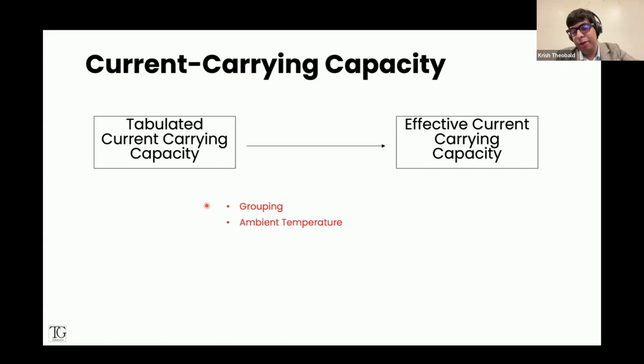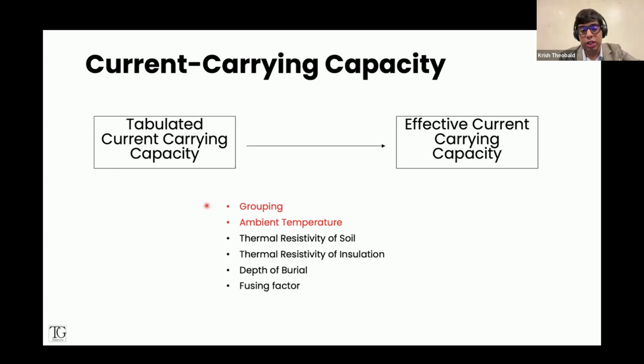Ambient temperature. So, what is the ambient temperature? The cable is tabulated to carry a certain amount of amps. It's tabulated to do so rising from an ambient of 20 to the maximum operating temperature of 70. But if the ambient itself is higher, at say 40 or 45, then the cable cannot rise that much anymore. If you bury the cable in soil, the soil's ability to dissipate heat is also a factor. And if you have surrounding insulation, that's also a factor. A lot of new buildings are seeing this now. Obviously, how deep you bury it also matters. And if you're using a fuse, such as an HRC fuse or a KitKat fuse, then there are certain other factors that kick in as well. I'll show you some more details.